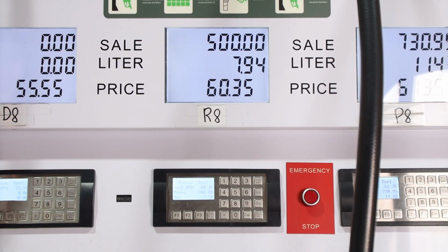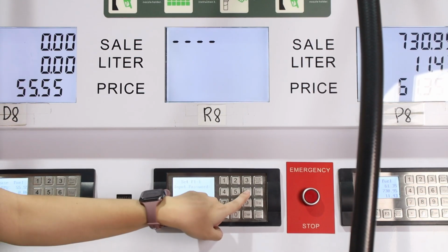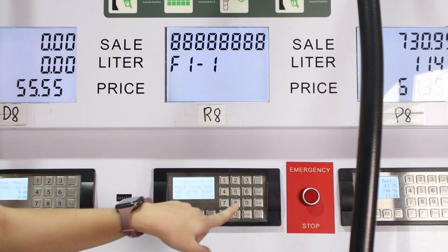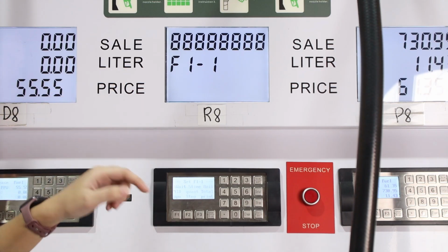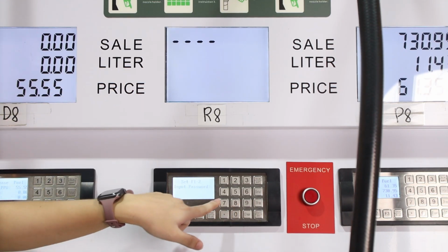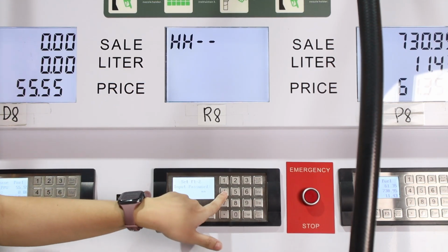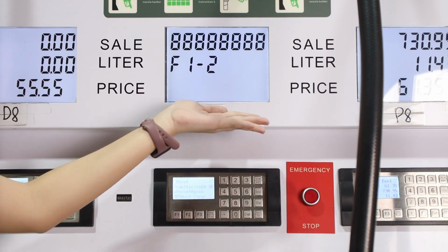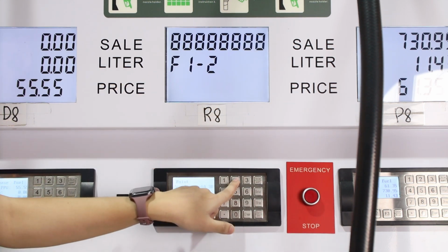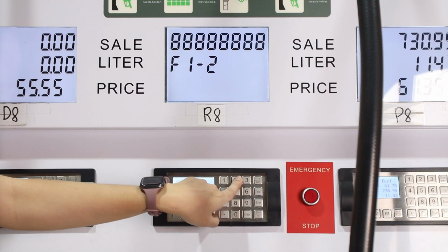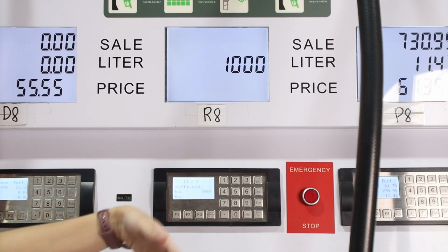Enter calibration mode. On the keypad, press F1 and input the level 1 password 6267. The display shows 88888888 F1-1. Press the 0 key. Input the level 2 password 0047. The display shows 88888888 F1-2. Press 2 key to display the existing calibration value, e.g.